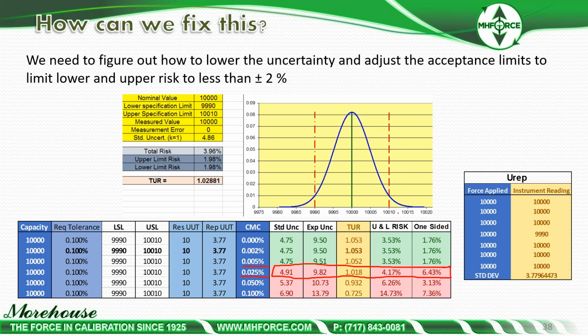Or you can take care of it on the side as the calibration laboratory. I'm a much bigger fan of that. And you can say, hey, look, we can calibrate this. This is what it is. This is your risk. Know that you have X% at 0.25. Know that you have a 6.43% chance of being out.